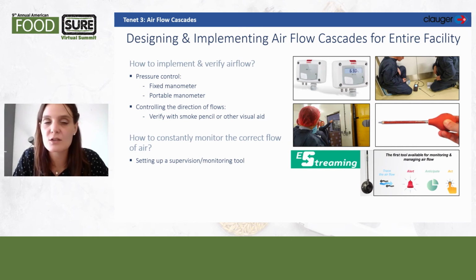it's a lot of consumption of energy because you have doors always open and you have product between each room. So it is recommended to control the direction of flow for food facilities with a smoke pencil, or we can also use a velocity sensor, and then you can register the velocity of the air between 2 different areas.